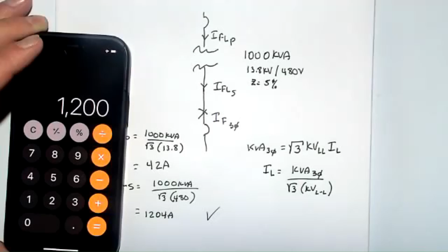So there's a good rule of thumb that basically says if you have full load amps on a 480 volt system, it's about 1.2 times the kVA rating of the transformer. Now, let's take this to the next step, which is how do I calculate my fault current? So if I want to calculate my fault current, I three-phase fault, it's actually very simple. All we do is we take I three-phase full load amps secondary, divided by the impedance in per unit.